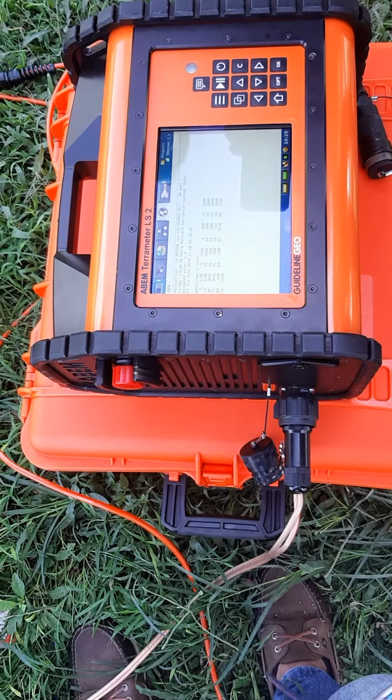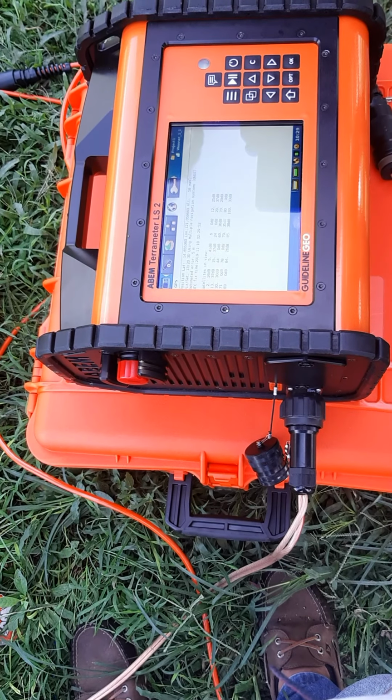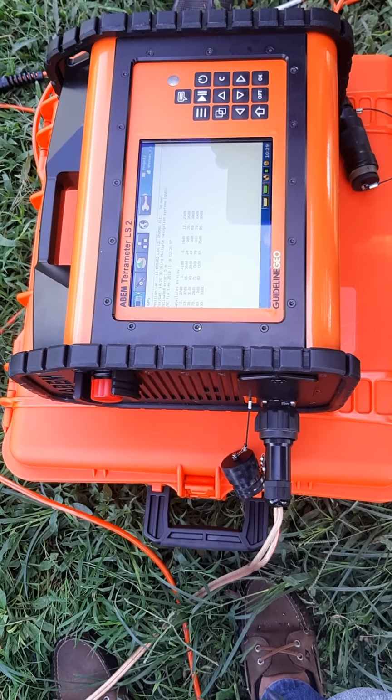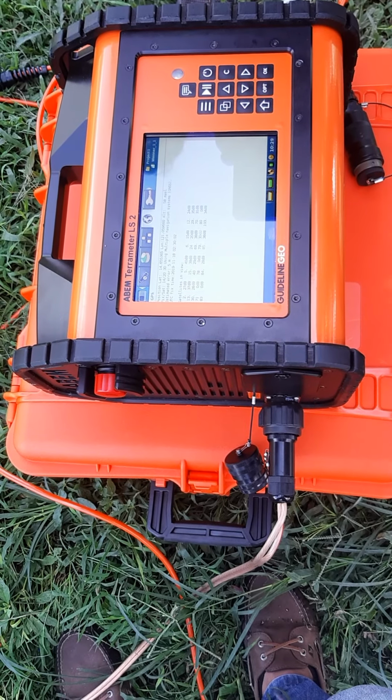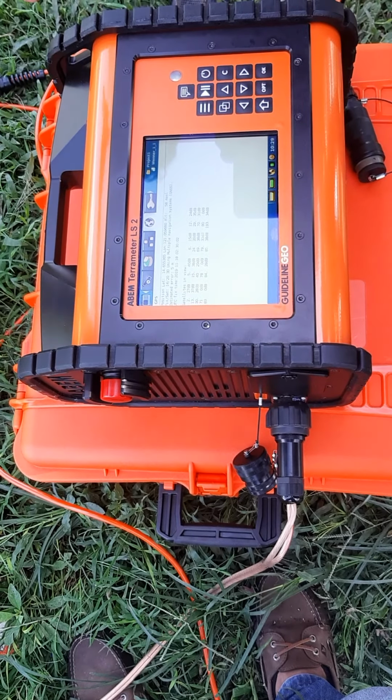Because you have a slope condition. If you have a steep slope, the cables will be shorter. But in terms of real distance, it will be the same, but in terms of slope topography, it will be shorter. This is part of the topography elevation. So in the calculation, it's 1 meter, 1 meter. But in terms of slope or elevation, it will be different. In horizontal, it doesn't matter.